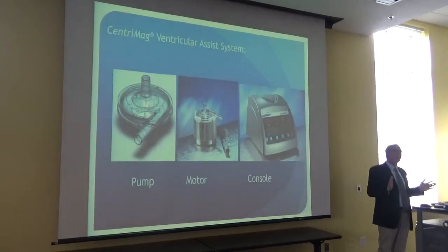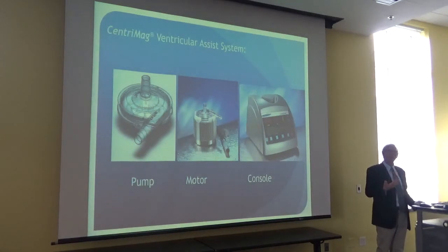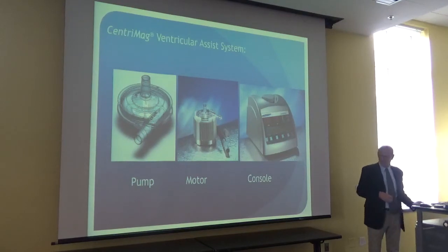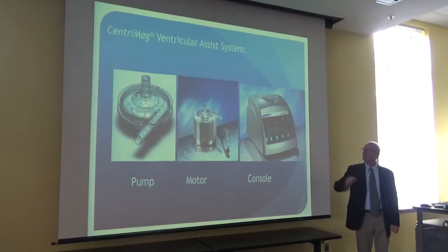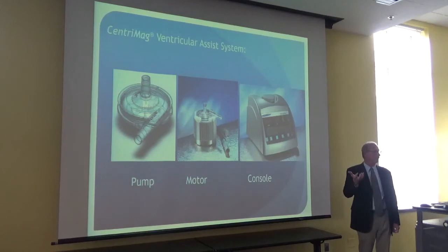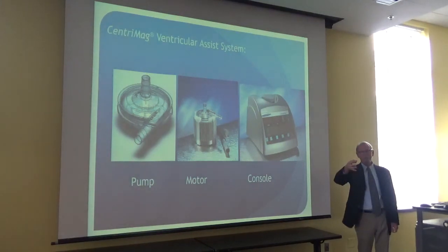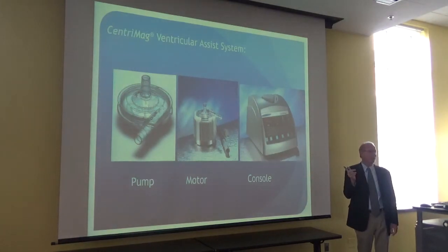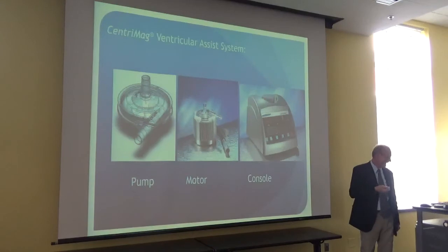But now let's get to the point. We're going to focus on a problem that happened with the CentriMag system. Just so you know more about it, CentriMag was comprised of a pump—only a five-part pump. It has an upper and lower polycarbonate housing, and inside it has a three-part assembly including the vanes, the magnet, and a cap. So it's five parts total. It costs us $40 to make it, and Thoratec sells it for $12,000—a pretty good margin on that device.